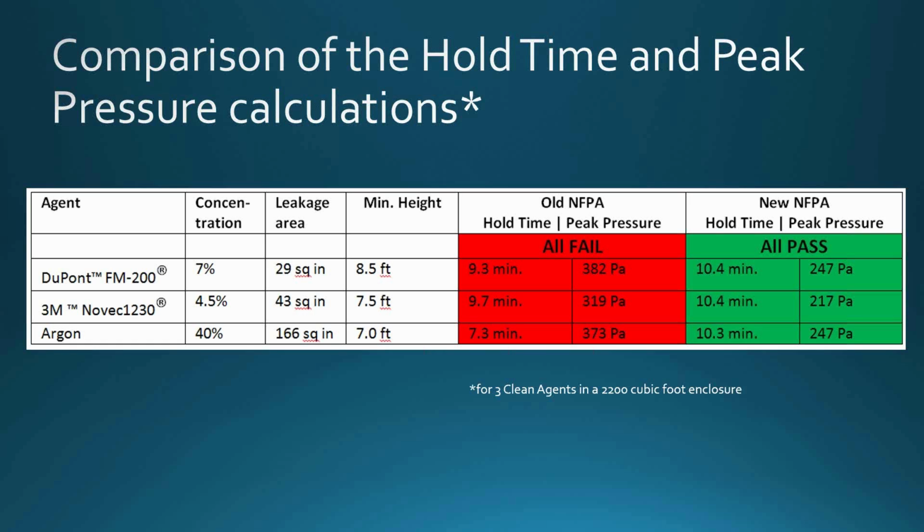You notice that the advantage is not quite as great when it comes to the halocarbons. We're picking up like 10% one way and maybe 20% the other way. But in a lot of cases, there could be a lot of cost involved in getting these enclosures a little bit tighter. And in some cases, it might be virtually impossible.